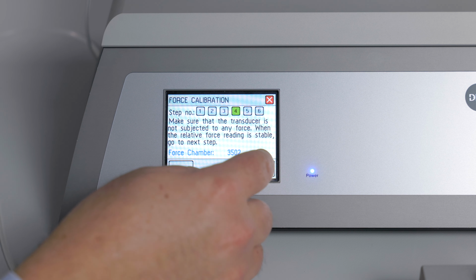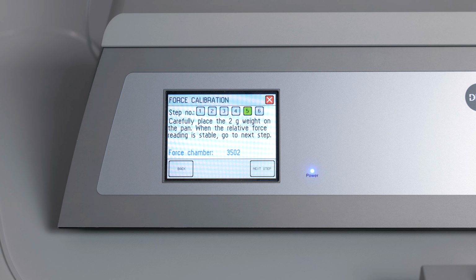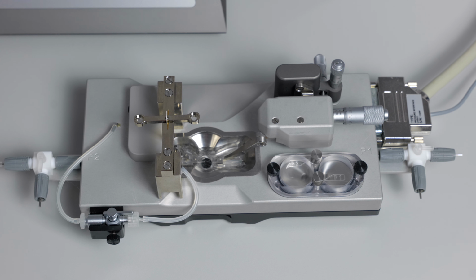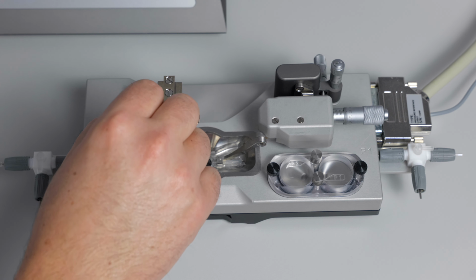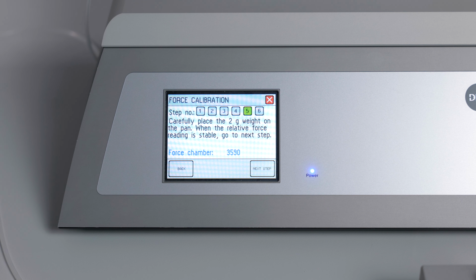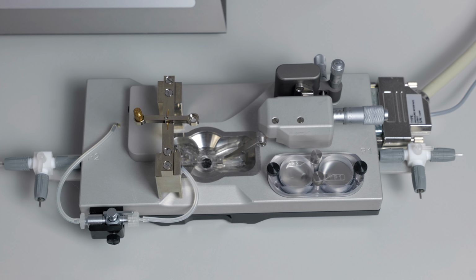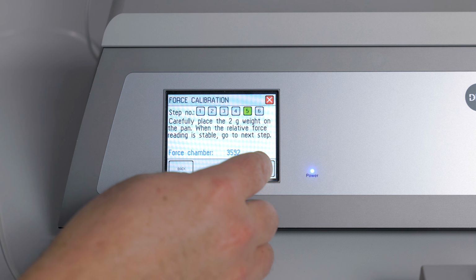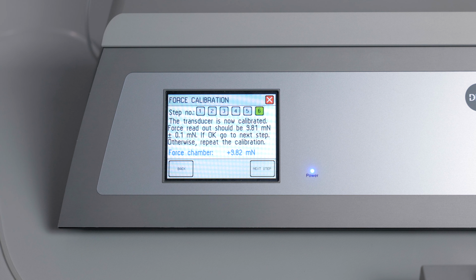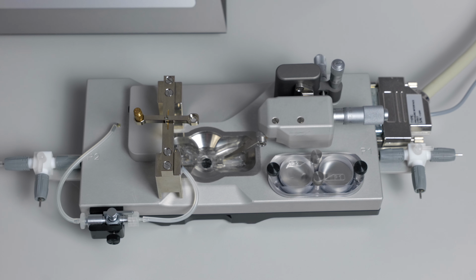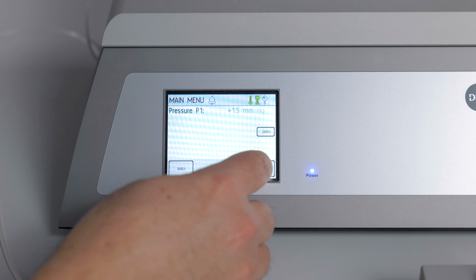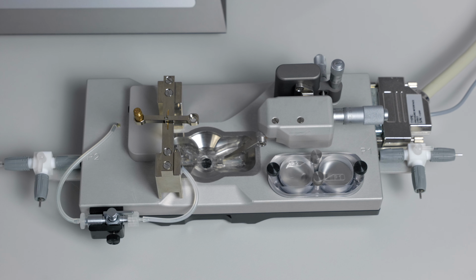Press next step. Step 5 asks you to place a 2-gram weight on the back pan of the T-balance. This will simulate a vessel pulling on the cannula mount. Let this sit for roughly 10 seconds to ensure that any movements have settled. Press next step, and this should be right around 9.81. If it's within plus or minus 0.1, that's fine. Press next step to complete the calibration.